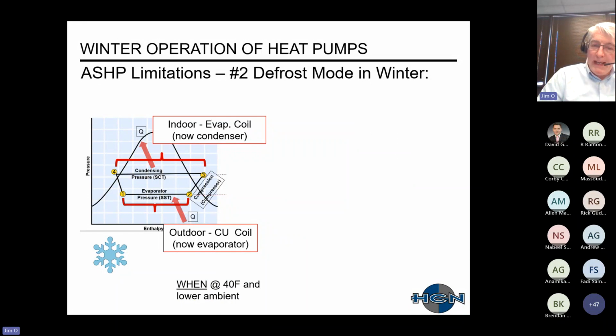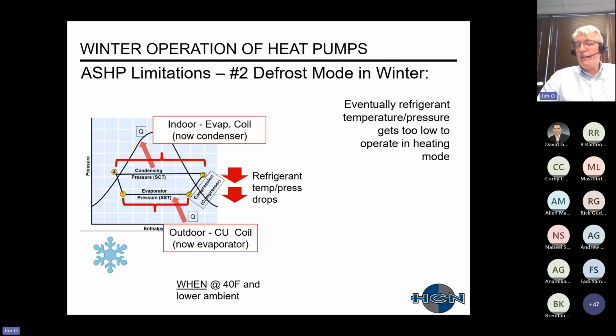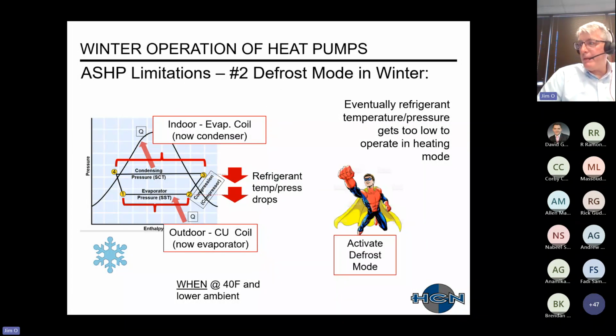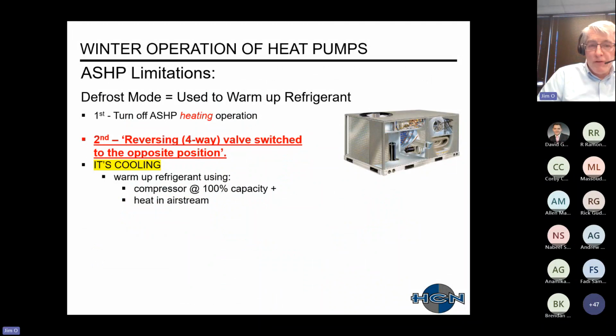Now, what will happen when the outside air temperature is at 40 degrees and it starts getting lower and lower? Our refrigerant temperature, slash pressure, will end up dropping. We'll eventually get to a point where the heat pump has run so much and the air temperatures have gotten so cold that your refrigerant temperature will get too low in heating mode, and the unit won't be able to safely or properly operate. So the rooftop unit or your split system, actually your air source heat pump, will activate what's referred to as defrost mode. All right, so what is defrost mode?